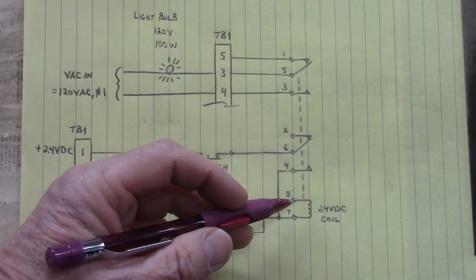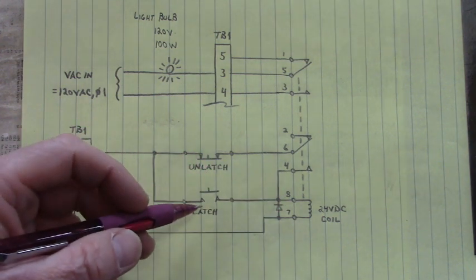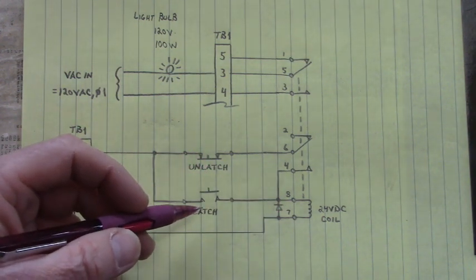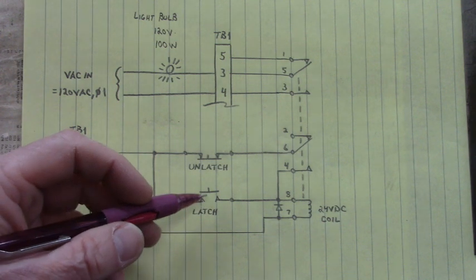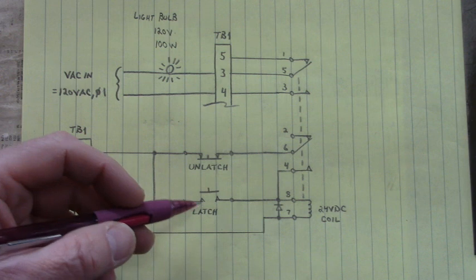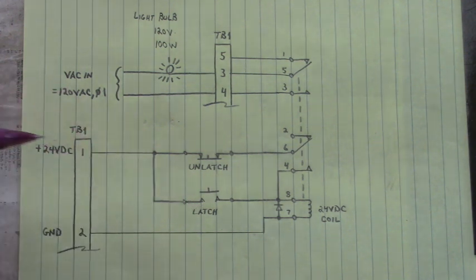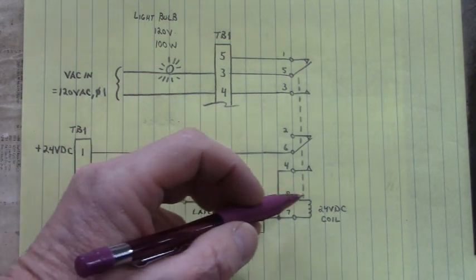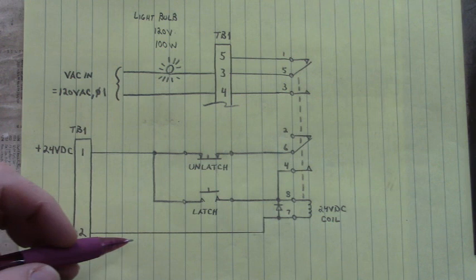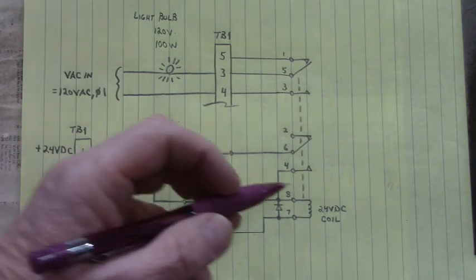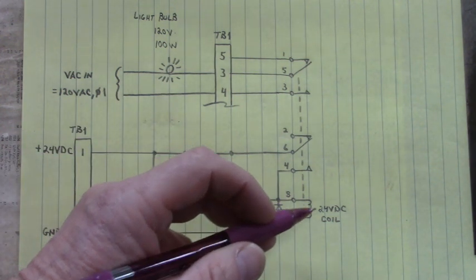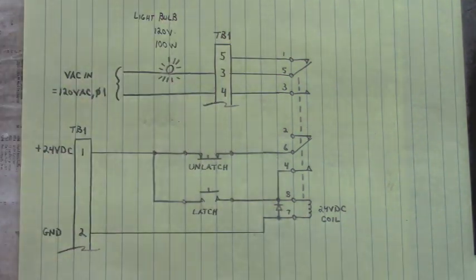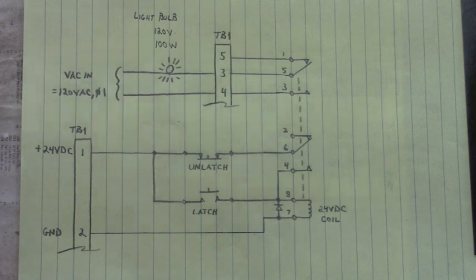This relay is set up to self-latch when I push the latch button, or we could call it a start button if you wanted to. The green button when closed will route this current from the 24 volt DC power supply, that's an external power, through the close button, through the coil, and back to that external power supply's ground, creating a magnetic field in this coil that will pull the contacts closed.